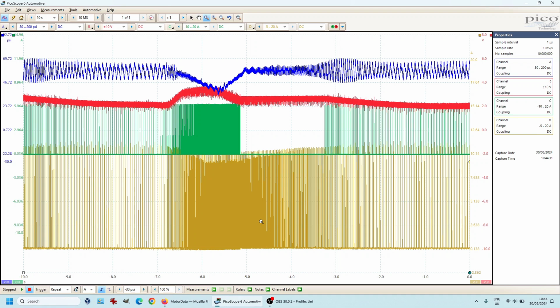Now, before we condemn the pump, all we have to do is go back to the low side and measure our powers and grounds to that pump. We want to make sure the power supply is steady to the pump. If the power supply is steady, then we have a bad pump. If it's not steady, then we have to interrogate that line and see why we have this problem. But right now, we are done.